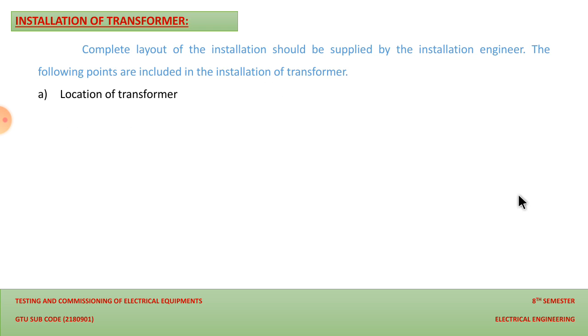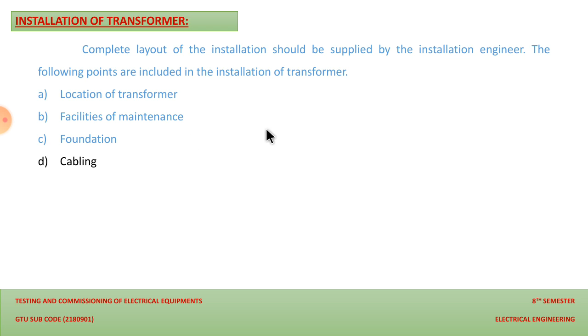Third is foundation. The foundation of the transformer must be proper according to the weight and size of the transformer. And the next point is cabling. So cabling must be proper. It should be clearly visible from the outside, so we can easily see all the wirings of the transformer. It should not be hidden, because of maintenance purposes. The next point we should keep in mind is the bushing and the cable box. So yes, we should take proper care of bushings and the cable box. These two are the most important accessories of the transformer, so we should keep in mind the safety of the bushings and the cable box. And the fifth point is connections. So you should keep in mind all the delicate connections of the transformer while you are installing it, so they will not get damaged.